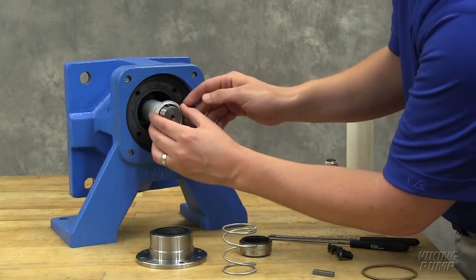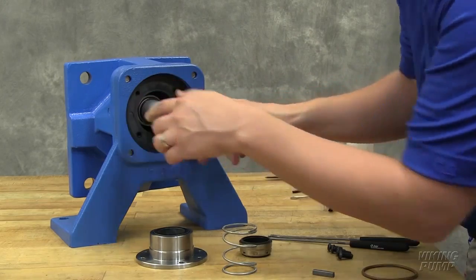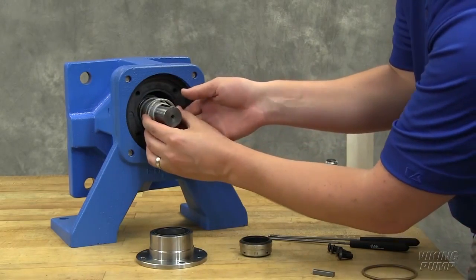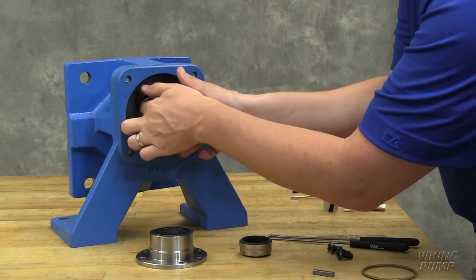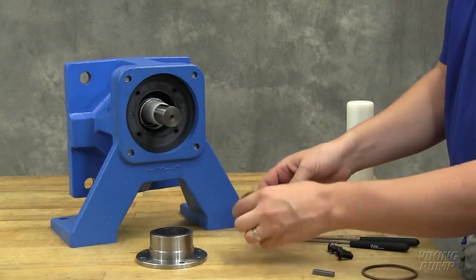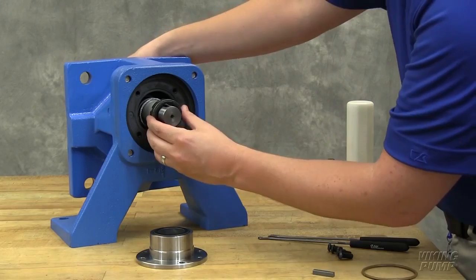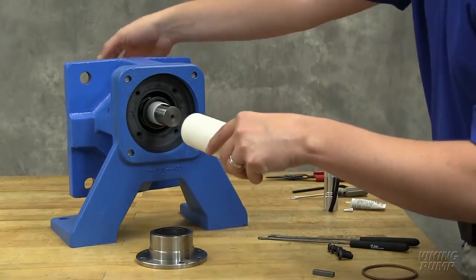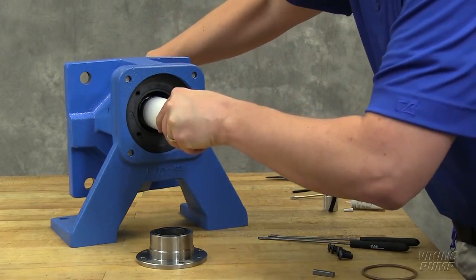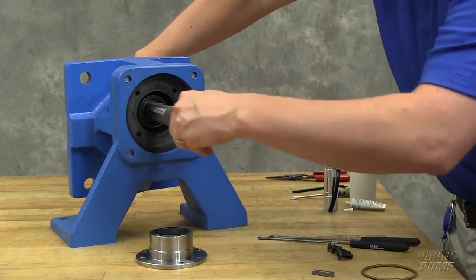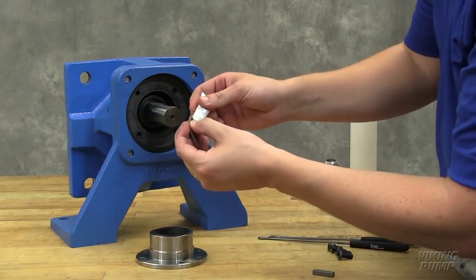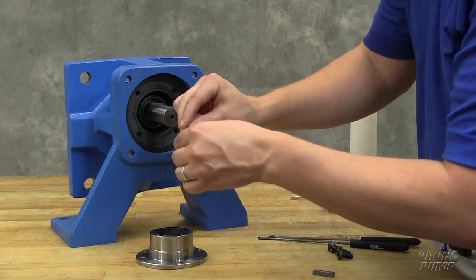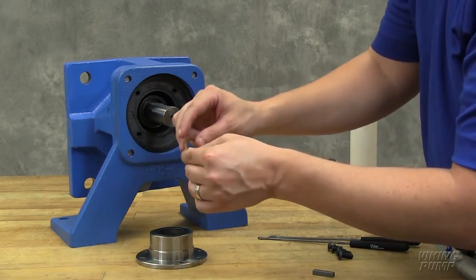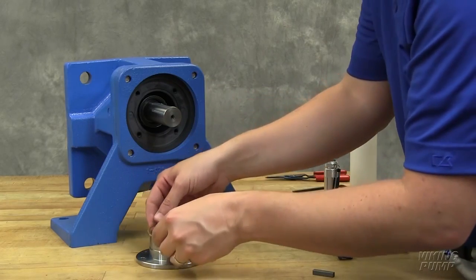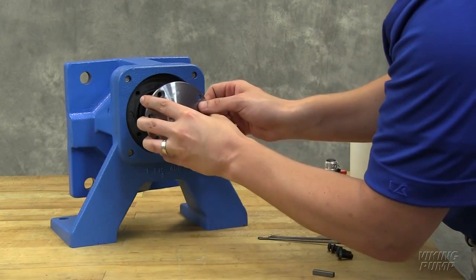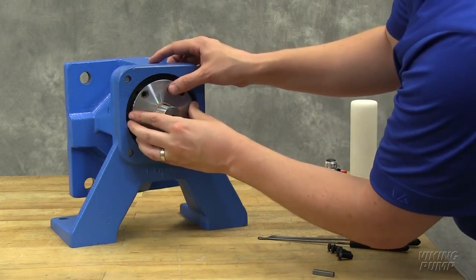Install the mechanical seal's spring holder onto the shaft with the flat face against the seal washer. Place the spring onto the spring holder with the inside diameter over the holder's step. Slide the bellows and rotating face over the installation sleeve onto the shaft. Remove the installation sleeve. Lubricate the O-ring with a light oil and place it onto the seal holder. Install the seal holder into the pump bracket.